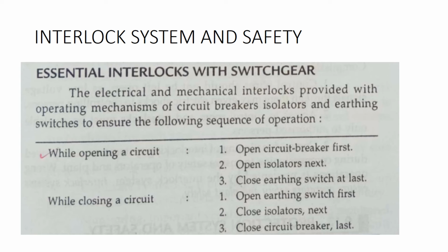The essential interlock for switch gear, as we all know: if we have to open a transmission line, first we have to open the circuit breaker. Then only we have to open the isolator. After opening the isolator, we have to close the earthing switch. Then we can climb on the transmission line for some maintenance activities. If we are not following this, and instead of opening the circuit breaker first, we open the isolator, there will be a huge arc or flashover that can damage these insulators and all.